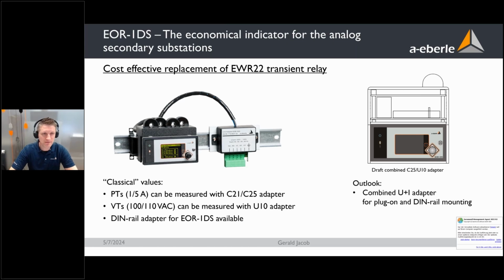In addition, the device can also measure directly PTs and VTs values, so classical values, as you might know them from primary substations. Therefore, you need certain adapters called C21, C25 adapter for the current, or the U10 adapter for the voltage measurement. It's also possible to equip the device with a DIN rail adapter to mount it on a DIN rail directly, as you can see here on the left side.